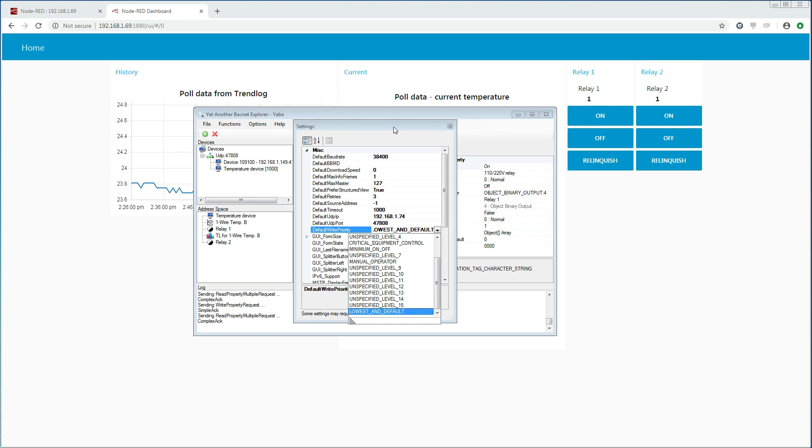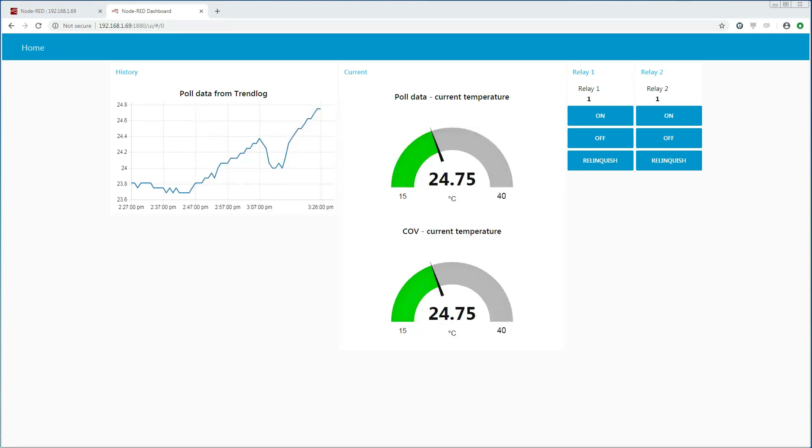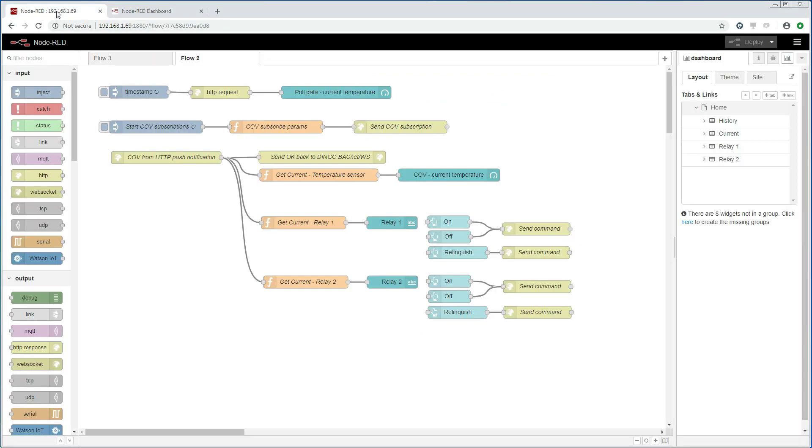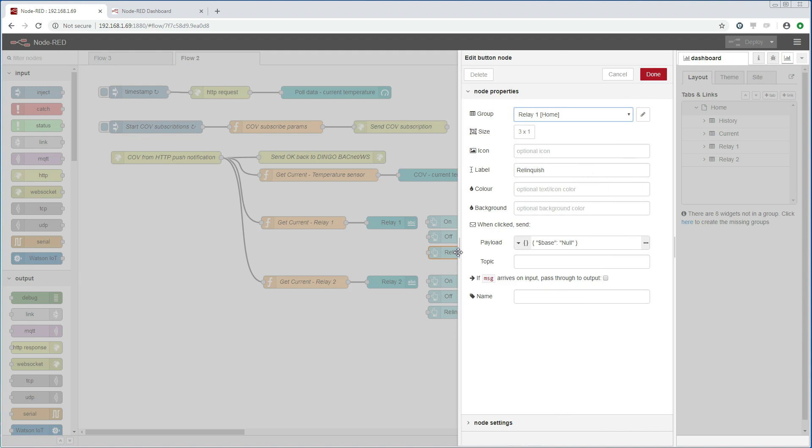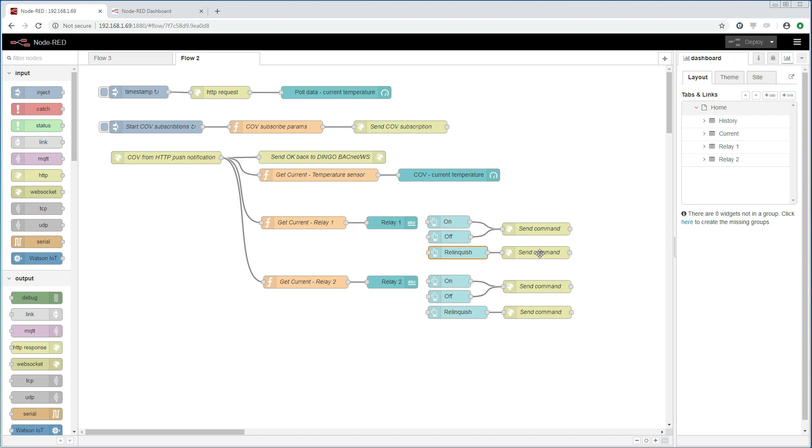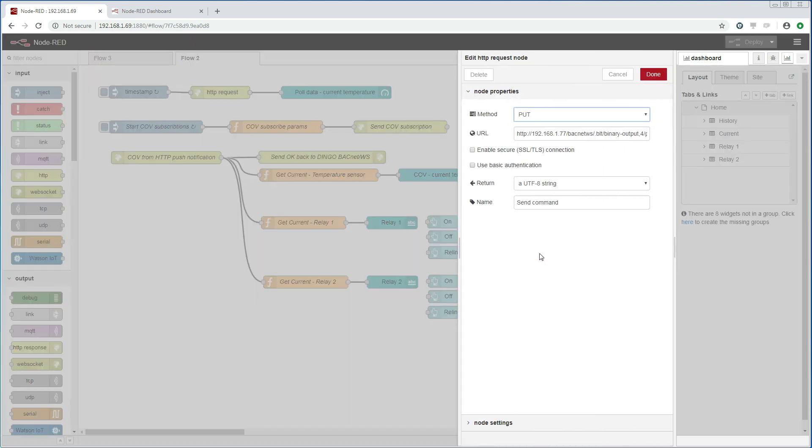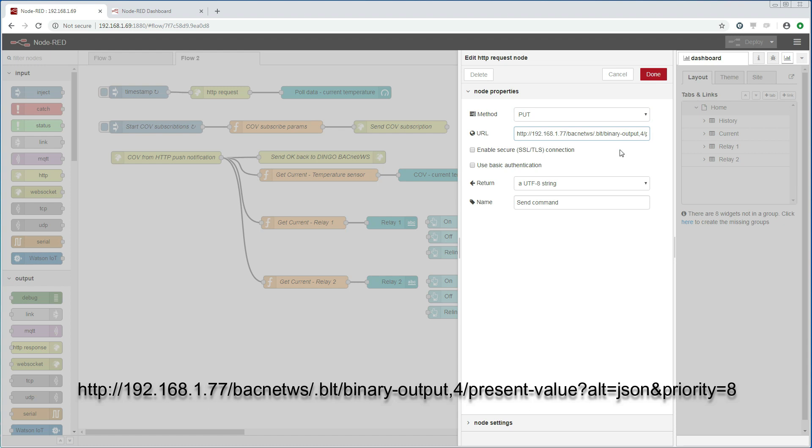I am going to show next how we relinquish the property. I have created another button called relinquish. The way to relinquish a property is by writing a null value to it. There are two ways to write a null value in the BACnet web services, either by using XML or JSON. I am using JSON and the payload here shows how that looks like in JSON. We then send the value via an HTTP request using the PUT method. The URL is a little bit different because we are now using JSON and it is of course important that the priority level is the same as when we were writing to the property.